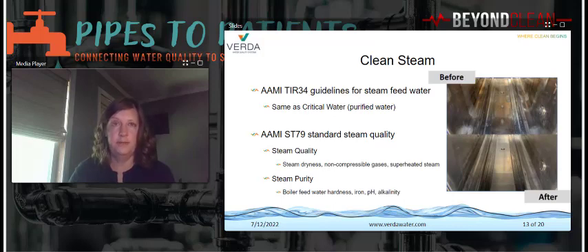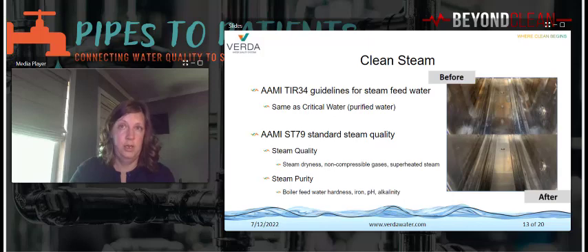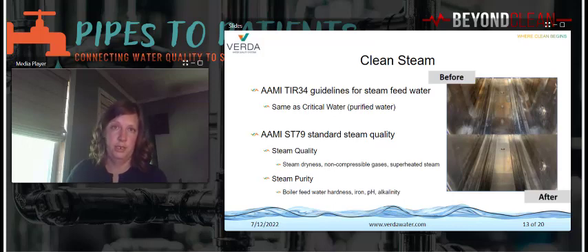However, if the incoming water quality is deficient, then facilities will be faced with steam filters quickly building up contaminants, potentially clogging within days, more frequent but less effective boiler blowdowns, and ultimately still chasing defects and dealing with frequent reprocessing rework in their medical device reprocessing. Clean steam is steam generated from purified water, most commonly from reverse osmosis filtration or deionization treatment. Instead of requiring multiple chemical treatments such as anti-scaling, pH control agents, neutralizing amines, or alkalinity builders, the purified water has significantly reduced contaminant levels, simplifying the water conditioning.